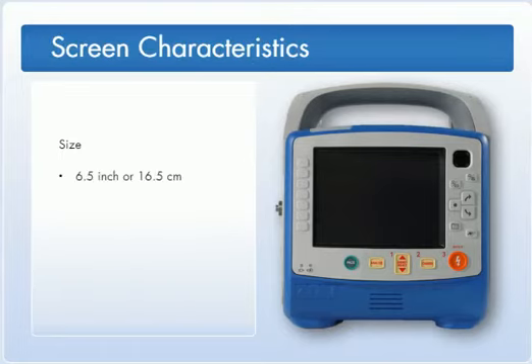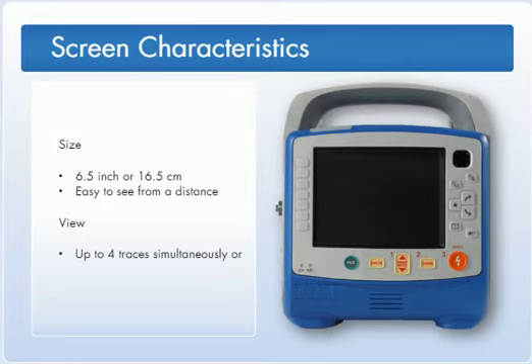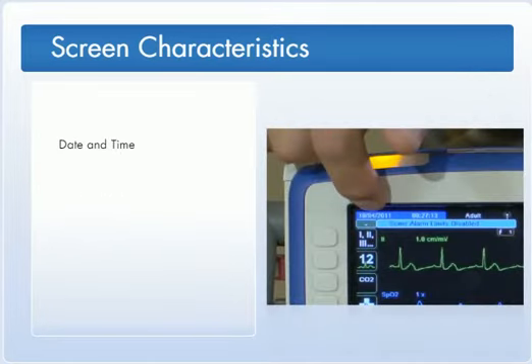The large 6.5-inch or 16.5 centimeter screen is very easy to view in a variety of environments and from quite a distance. It can simultaneously display up to 4 physiological waveforms or all 12 leads of a 12-lead ECG, and the numerics are very large. The X-Series displays the current date and time on the top left corner of the screen, which is easy to see and easy to adjust. To access the Date and Time menu, highlight the Date and Time display with navigation keys and press the Select key. This can be done from the standard monitoring screen.